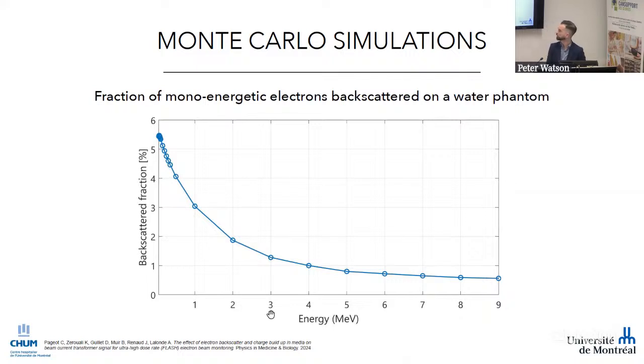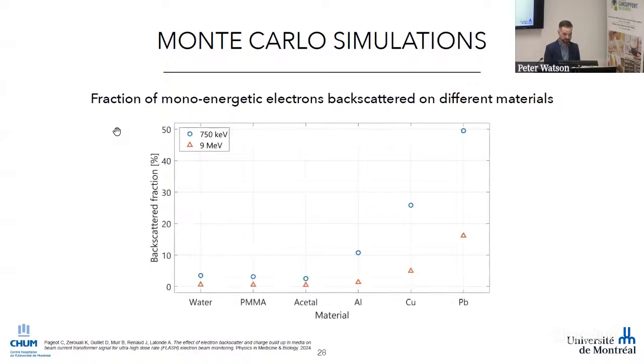And even if we consider very low energy electrons, it's never more than 5-6% of the incident electrons that are backscattered. This is true for water, and it's also true for other materials. We've simulated water. Here I'm showing two energies: 9 MeV, the triangles in red, and 750 keV, the circles in blue. For water, PMMA, and acetal, which is the plastic the collimators are made from, it's all much less than 5% of the incident electrons that are backscattered. Actually, to get something close to the 20% we're observing experimentally, you need to irradiate lead, and that's not what we're doing. We had that just for solid water phantoms.